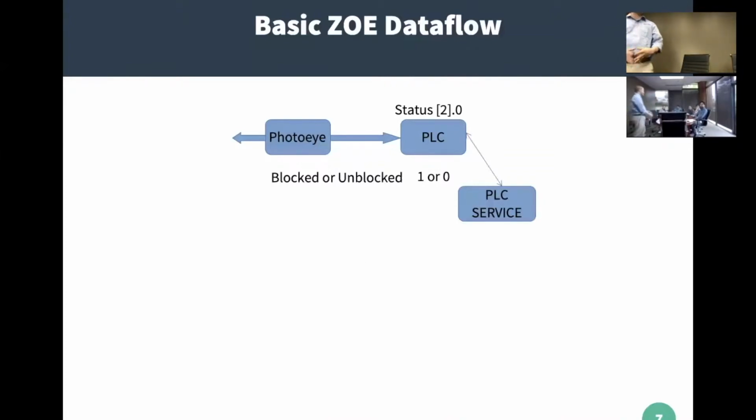So, like I said, we don't want all the HMIs to read this information because we could have 1 HMI, we could have 10 HMIs. If they're all reading the information at the same time, the information could be different, which isn't ideal. Also, we're doing 10 reads, or we could just be doing 1. So all of this information is read by the PLC service. The PLC service is reading that information and then broadcasting it out, if you will.